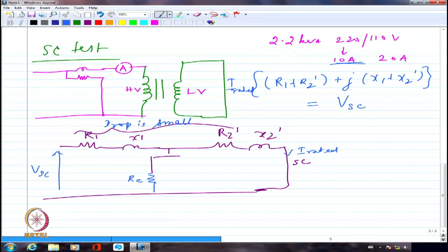Please note that IC has more influence on the losses than RC itself, because RC is power 1, whereas IC is power 2. So IC, I want to minimize. If I want to minimize IC, RC has to be increased quite a bit. So RC normally in a transformer will be like 1000 ohms, maybe more. The better the design of the transformer, the RC value will almost tend to infinity. It's not infinity. Compared to the winding resistance, it will be very, very high. That's all I'm trying to get at. So this will be some thousands of ohms.